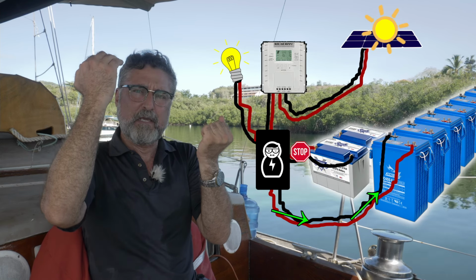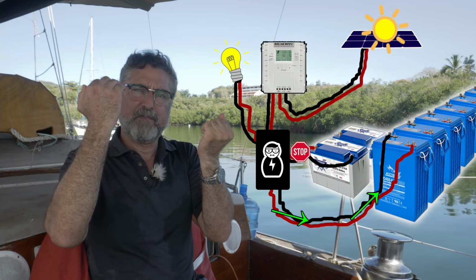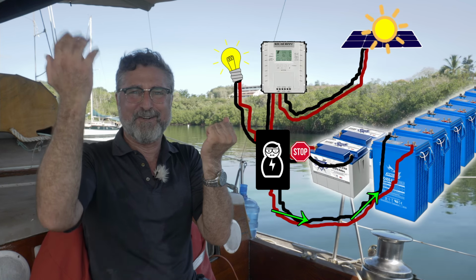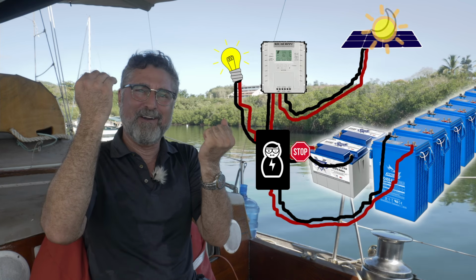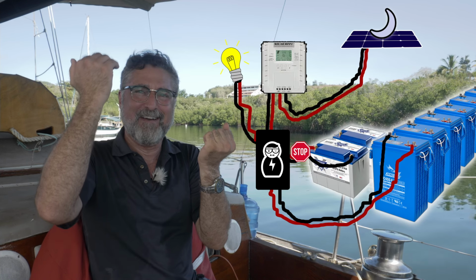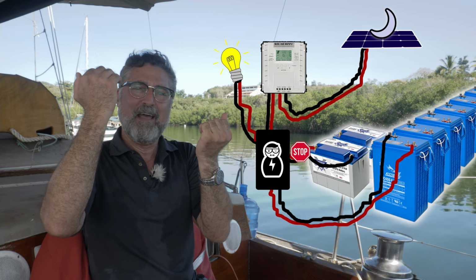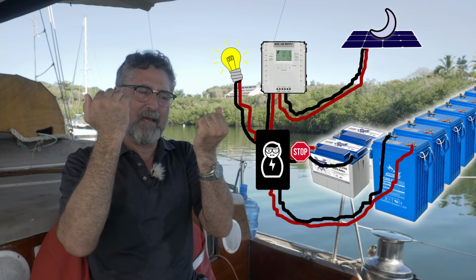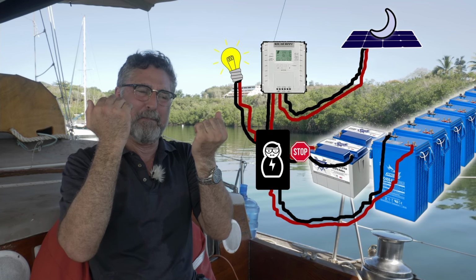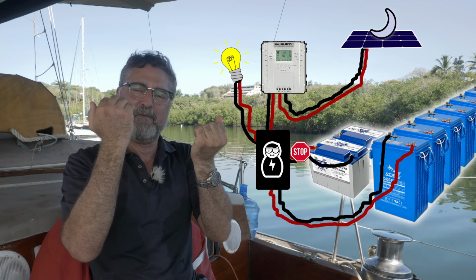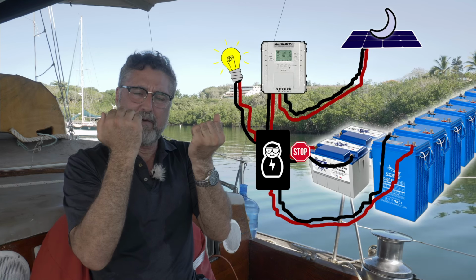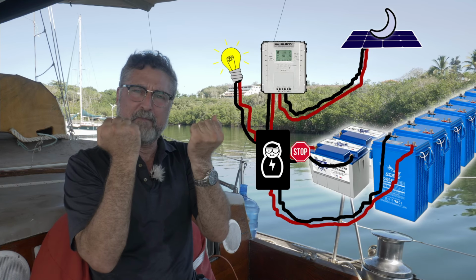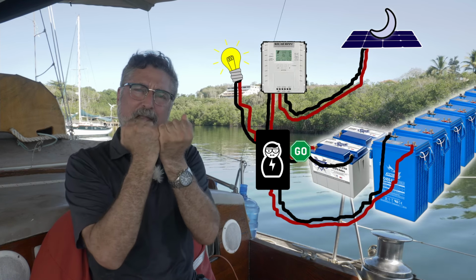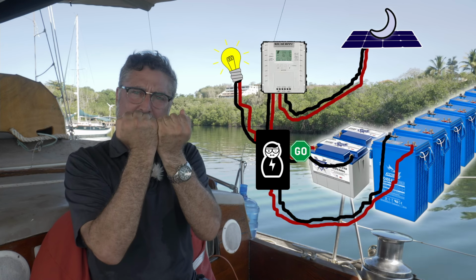Eventually the voltage will start coming down, either because the charge controller says the lead is done, or it got dark since the sun only stays up so long. The lead voltage will start coming down. The lithium's been creeping down a little bit, but not much, because it's lithium - it just kind of stays where you leave it. When they come back together and they're at the same voltage, it's safe to bring them back together. Now they're back together.